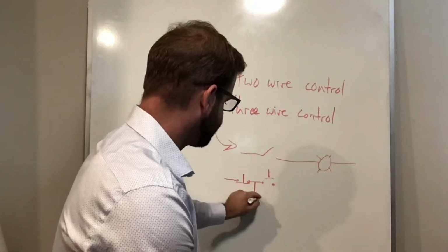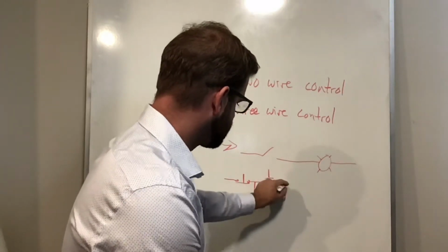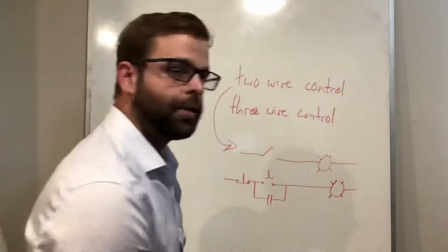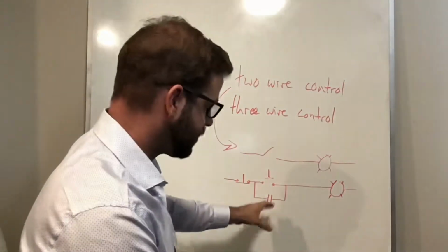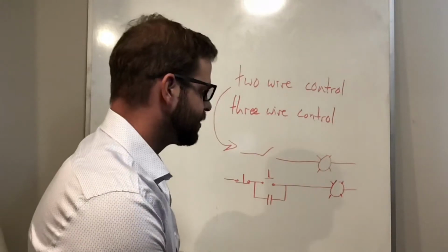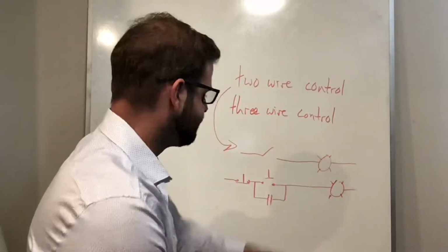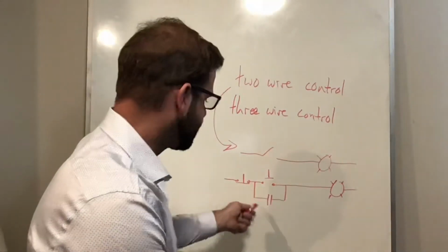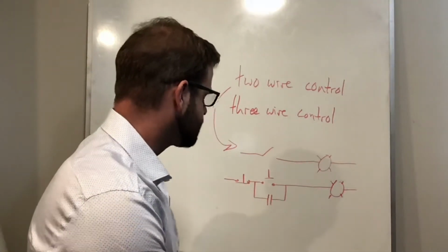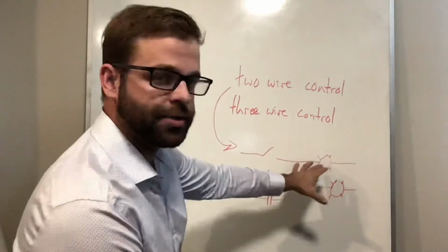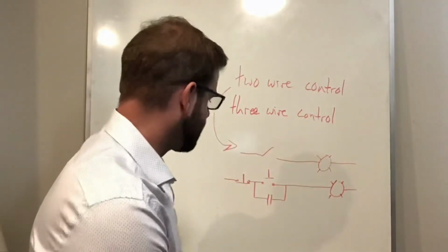And 3-wire control had a stop, had a start with a holding contact, and a pilot light. So know the terms of a holding contact, which latches the circuit. Know the symbols, know that that's a pilot light. Know that that's a normally open push button, that that's a normally closed push button. And so this would be a start, so it'd start your circuit. The stop would stop your circuit.